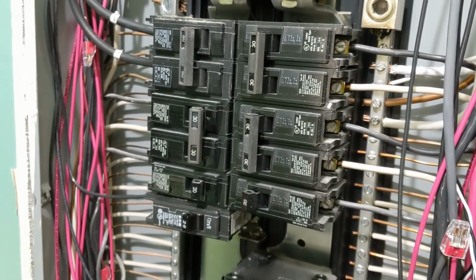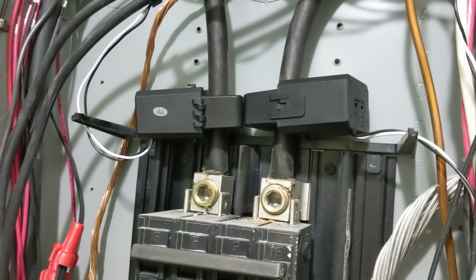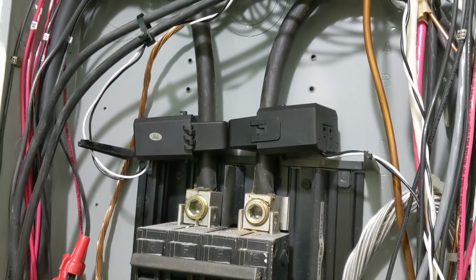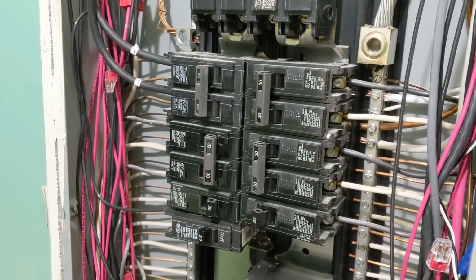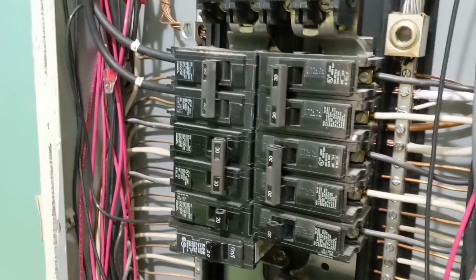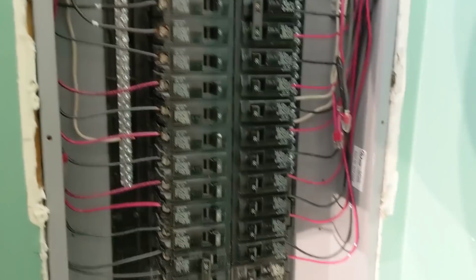But if you have extra power and you don't want to send it back because they're not giving you anything for it, then you can program limited power to home. And the cool thing is you can use excess power to run some of the heavy loads. Some of your double pole or your outdoor compressor condenser units can take that power and use it. Not to run it in an off-grid, but in an everyday situation, so you're maximizing your investment. And then here is just the critical loads panel. These are all the circuits that will run in this home or can run if the power goes out.